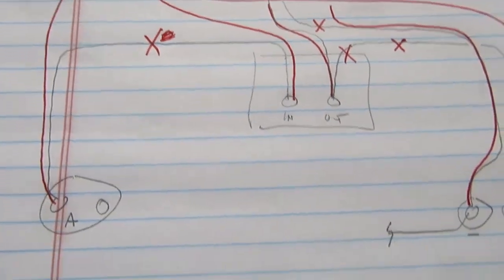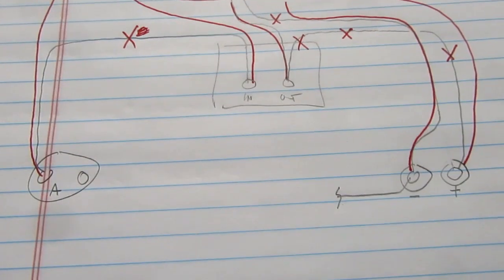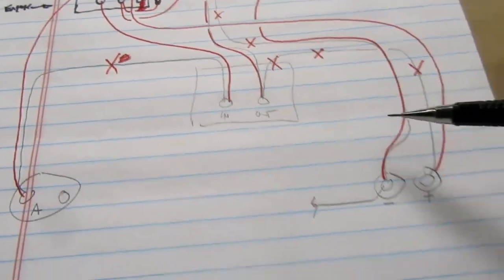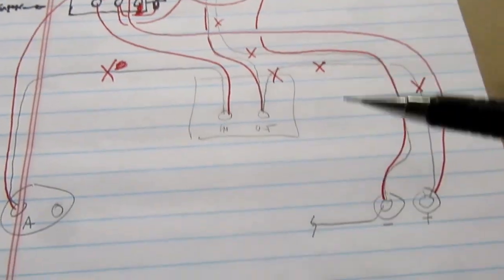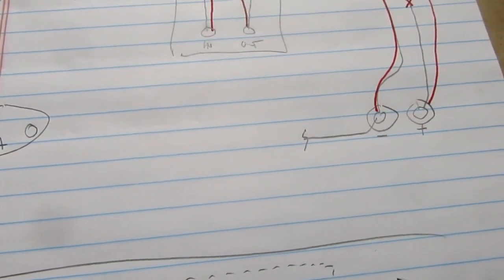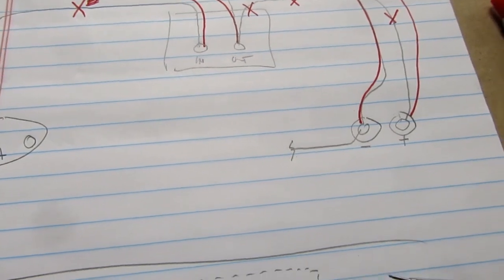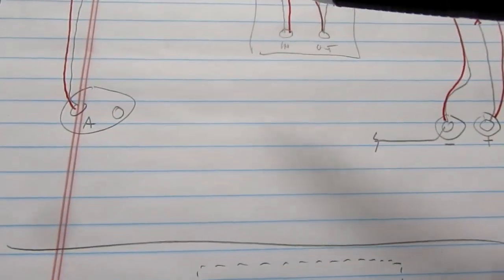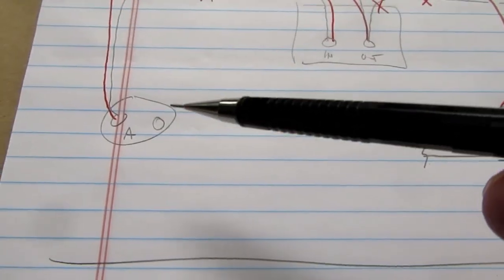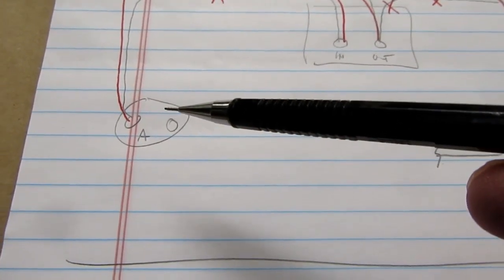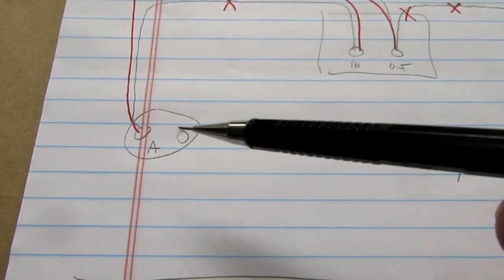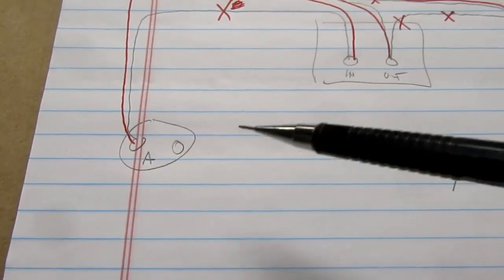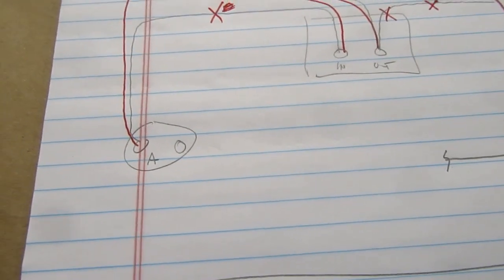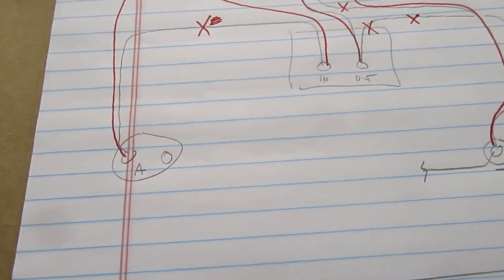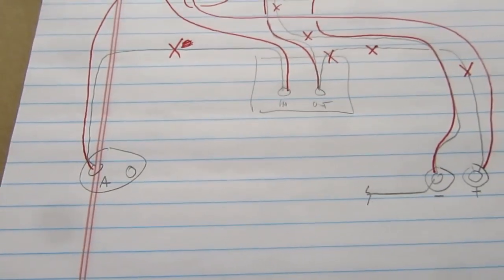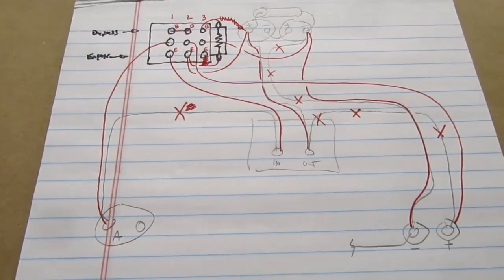And I'm planning on replacing all of the wiring. There's only a couple of them that I could salvage, like the one from the minus terminal up to the capacitors. Everything else needs to be replaced. And I'm replacing everything because the insulation rating on the conductors that the previous owner used appears to only be 200 volts, even though this is potentially a 400 volt circuit. So I have some wiring with 600 volt rated insulation, so I'm just going to rewire everything in this circuit.